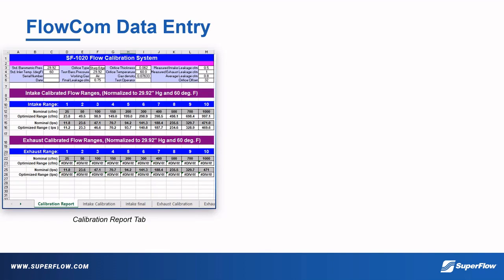Once all flow rates have been recorded and the % differences have been verified, switch to the Calibration Report tab. Here you will find the optimized numbers for both intake and exhaust calibration. On the Calibration Report page, find the intake range table. This is where the optimized numbers are found.